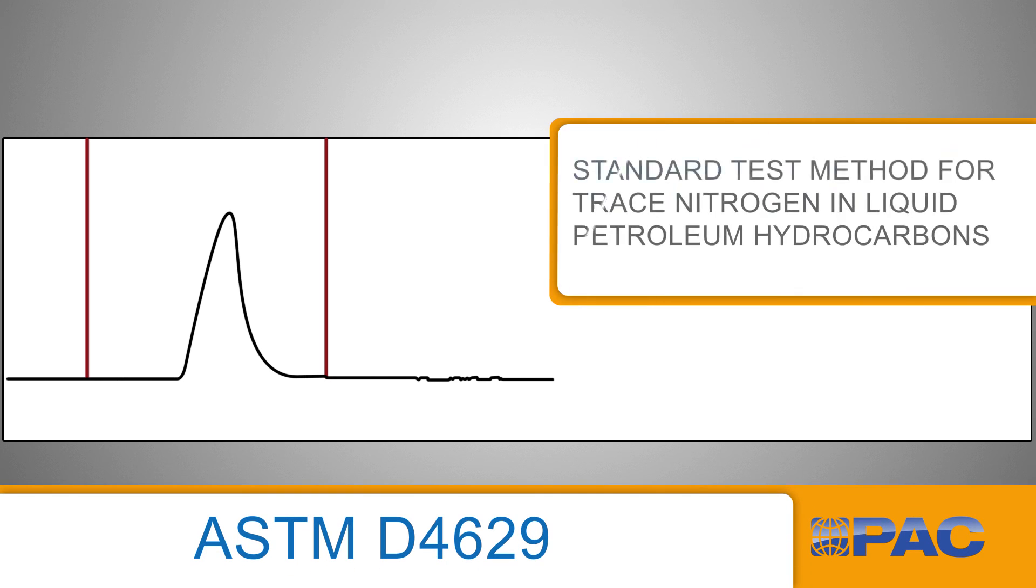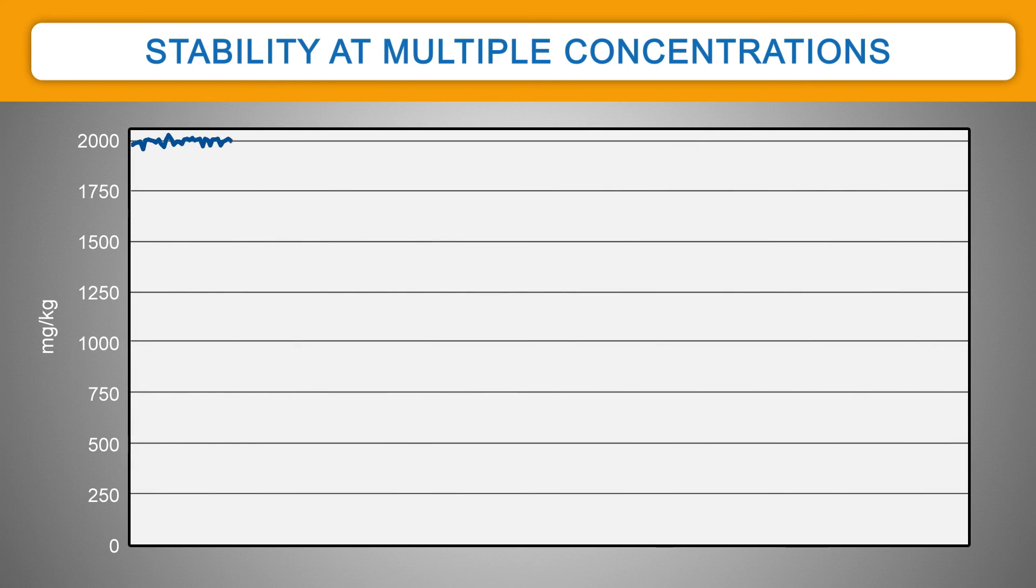The detection method is based on primary test method ASTM D4629 for high correlation to laboratory results. N-SURE can handle a wide range of products, including heavy diesel, by controlling the viscosity of the sample as it is injected.